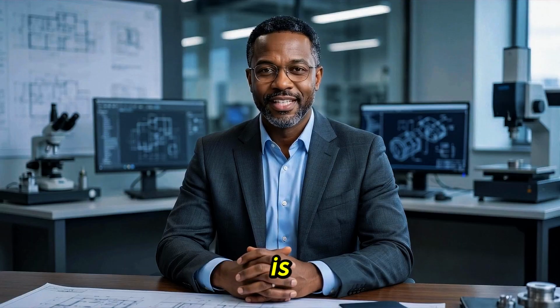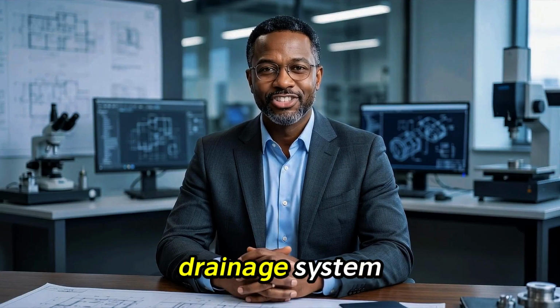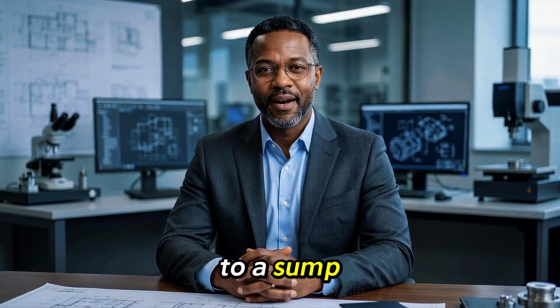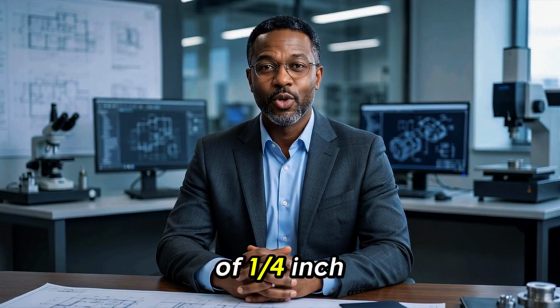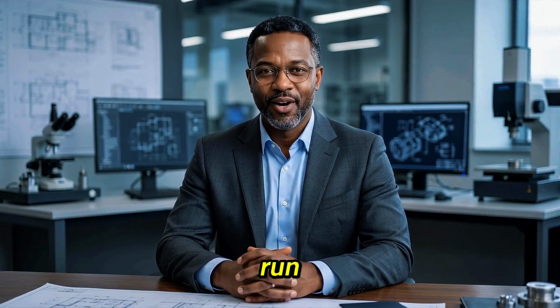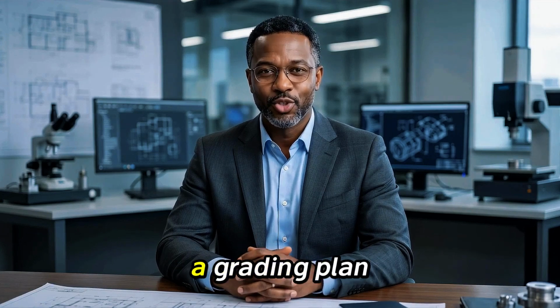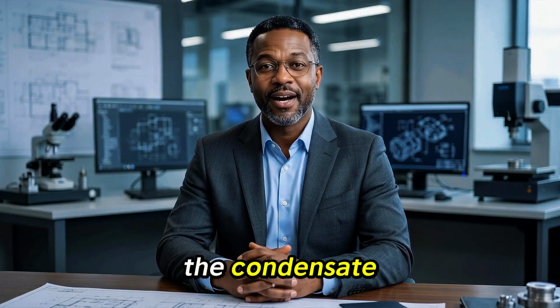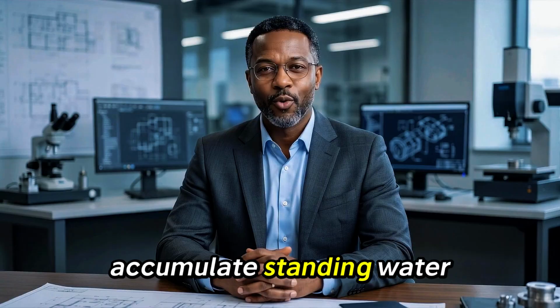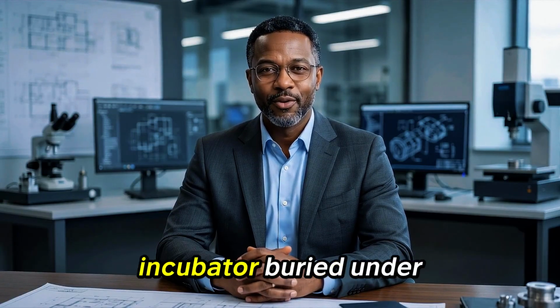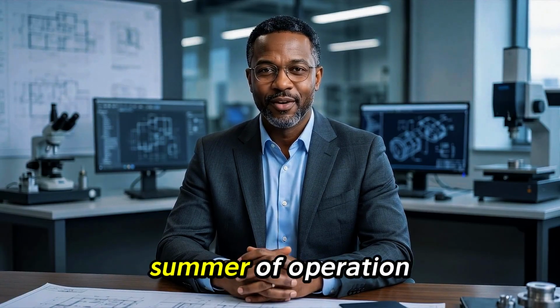The first question is whether the design includes a condensate drainage system with positive slope to a sump or daylight drain at a minimum of 1/4 inch per foot throughout the entire pipe run. If the contractor cannot show you a grading plan and a drainage endpoint for the condensate, the system will accumulate standing water, and you will have a mold incubator buried under your yard within the first summer of operation.